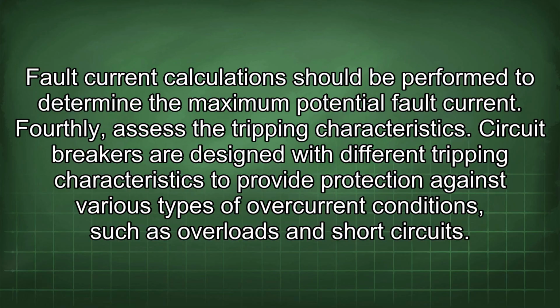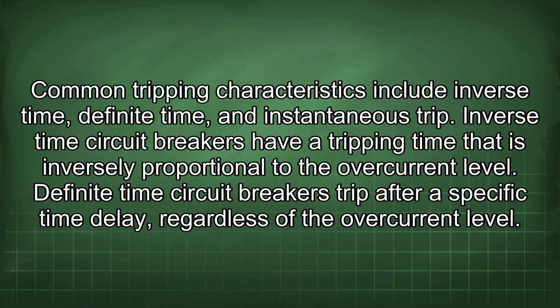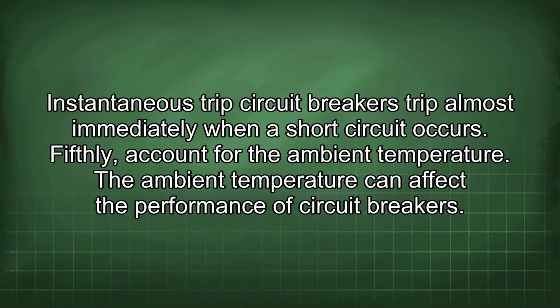Fourthly, assess the tripping characteristics. Circuit breakers are designed with different tripping characteristics to provide protection against various types of overcurrent conditions, such as overloads and short circuits. Common tripping characteristics include inverse time, definite time, and instantaneous trip. Inverse time circuit breakers have a tripping time that is inversely proportional to the overcurrent level. Definite time circuit breakers trip after a specific time delay, regardless of the overcurrent level. Instantaneous trip circuit breakers trip almost immediately when a short circuit occurs.